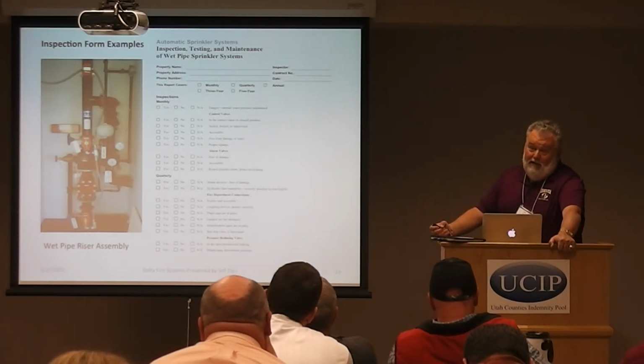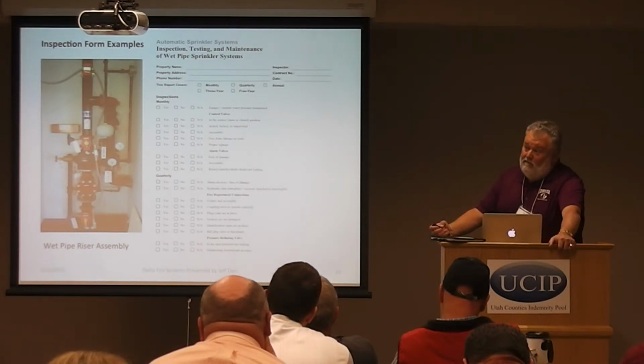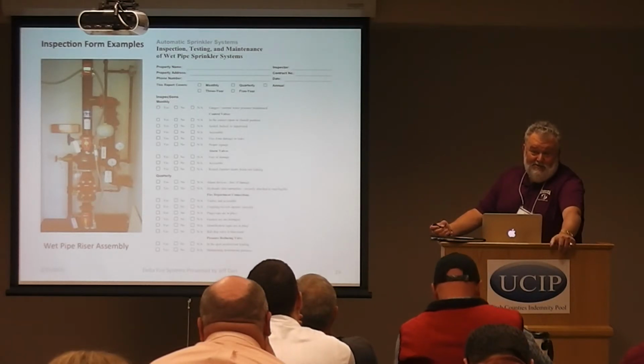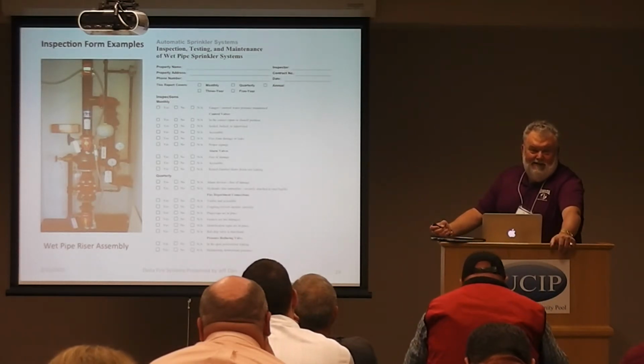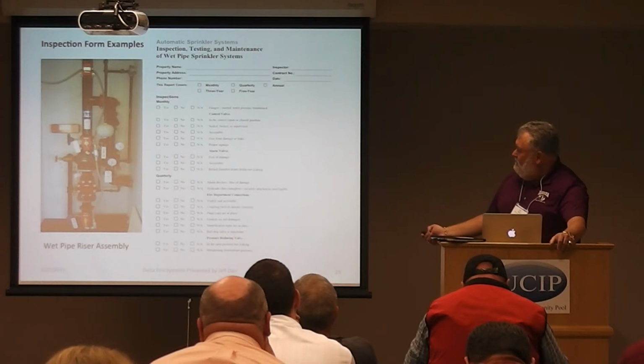You wouldn't believe the amount of times we've gone out to do an inspection and found the water supply shut off. They paved the road out the street, for instance, the year before. Well, they've gone over the control valve, paved over it, no one knows where it's at, but it's shut off. So little things like that you really have to pay attention to.